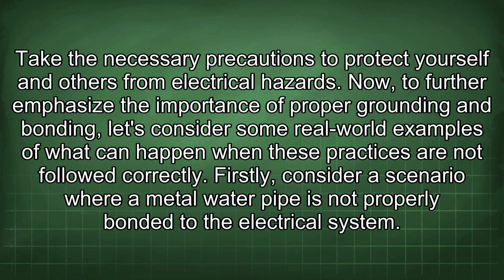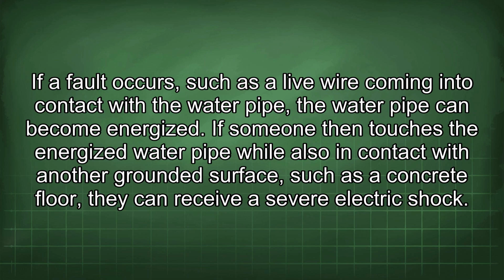Now, to further emphasize the importance of proper grounding and bonding, let's consider some real-world examples of what can happen when these practices are not followed correctly. Firstly, consider a scenario where a metal water pipe is not properly bonded to the electrical system. If a fault occurs, such as a live wire coming into contact with the water pipe, the pipe can become energized. If someone then touches the energized water pipe while also in contact with another grounded surface, such as a concrete floor, they can receive a severe electric shock.